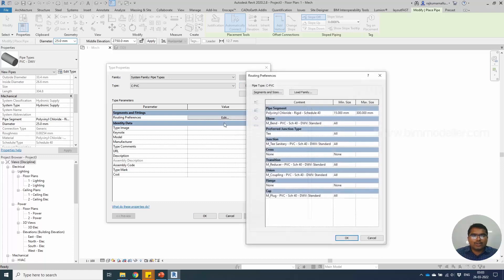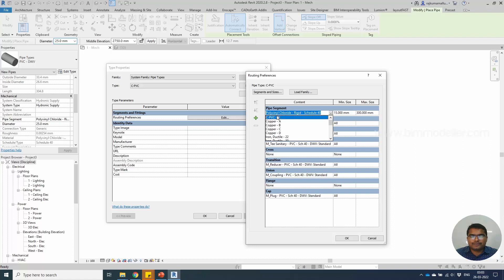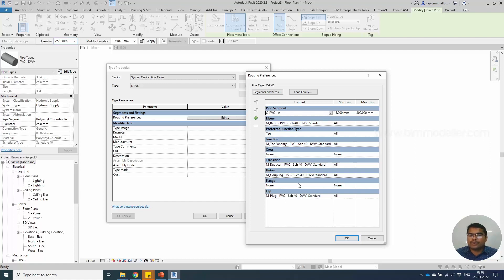Click the routing preference. You must change this segment to cPVC. Remember, all these fittings are currently related to PVC, and you need to have your own cPVC fittings based on your manufacturer. The manufacturer will supply each fitting like elbows, tees, and everything.